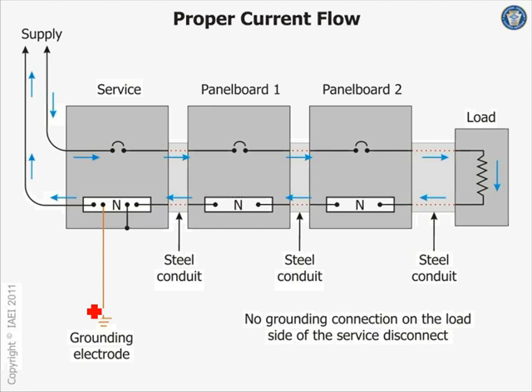So look at this, here's my plasma TV. I'm taking my service, 200 amp to 100 amp to 60 amp panel, all the way to a 20, 15 amp circuit feeding my plasma TV. Under normal operating conditions, the current goes right through the hot, right through the neutral, back to the source. That's how the system should work properly.